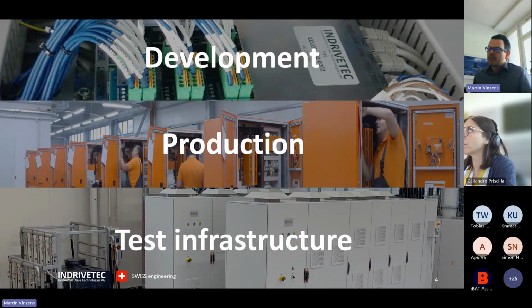As mentioned, we design and develop our equipment by ourselves. We produce it in our facilities, and we have quite some test infrastructure. Here in Zurich, we can test power electronics up to 1 megawatt. We have a heat chamber. We can do all kinds of insulation testing and power runs. Then in our facility in Bulgaria, we have a 6 MVA or 3 megawatt test stand, so we can run active and reactive power up to this level, up to 1500 volt DC, 690, 900 volt AC, and fully test our equipment.